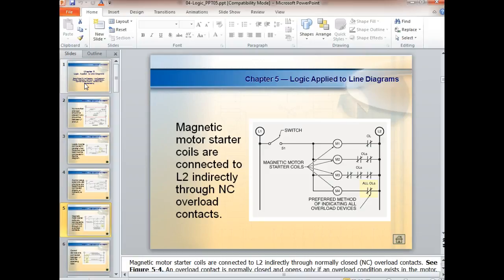So these are the overloads. This would be for a single phase. This would be for a single phase where we have overloads in both lines. This would be for 3-phase, but very often now, most of your motor starters has one overload contact that's tripped by all 3 phases. So normally, this is the only thing, by the way, that's allowed on the L2 side. So normally, what we have on the L2 side is the load normally connects to L2. The only thing that's allowed between the load and the L2 are overload contacts.